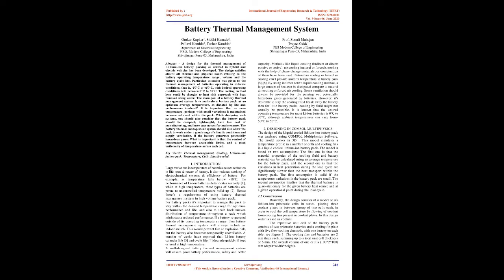The design satisfies almost all thermal and physical issues relating to the battery operating temperature range, volume, and the battery cycle life. Particular attention was given to the thermal management of batteries operating in extreme conditions, that is, -50°C to +50°C, with desired operating conditions held between 0°C to 35°C.